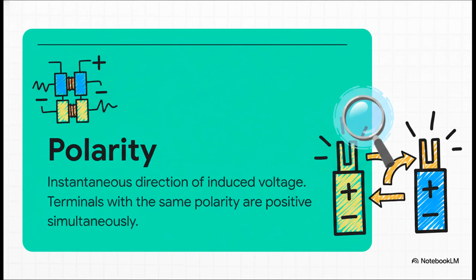The test is simple: connect the primary and secondary windings together in a series loop, feed AC voltage into one of them, then use a voltmeter to measure the voltage across the two open ends.